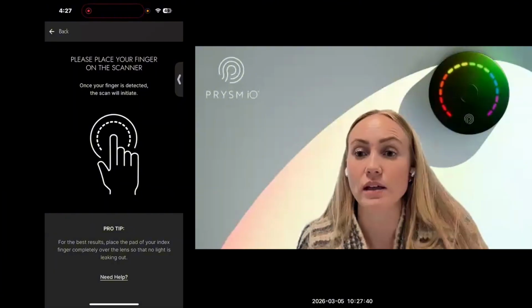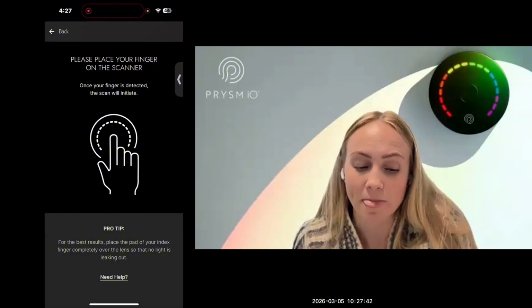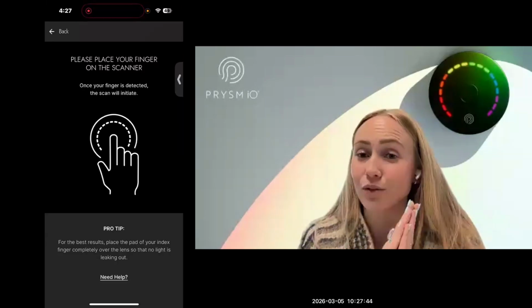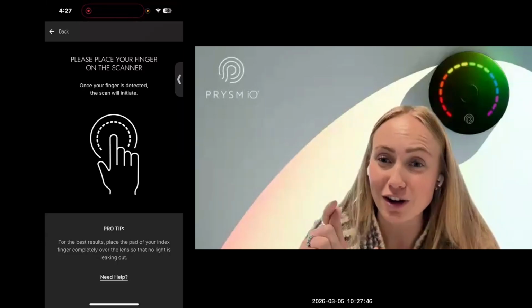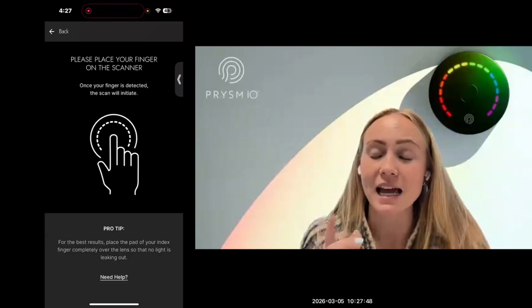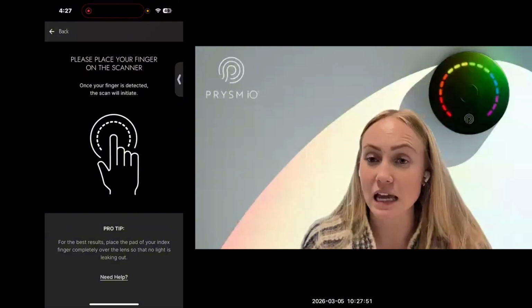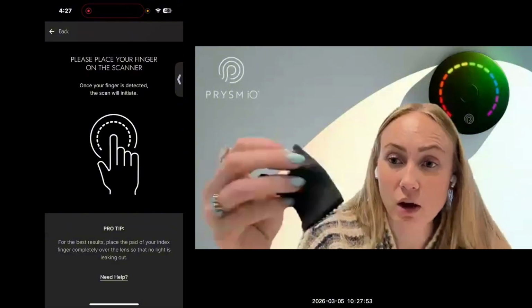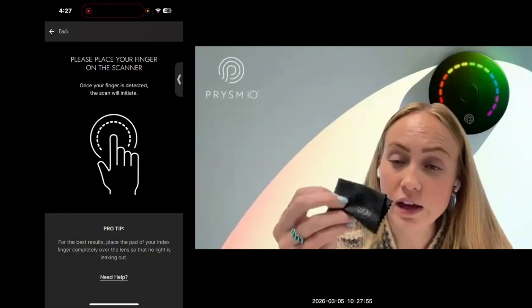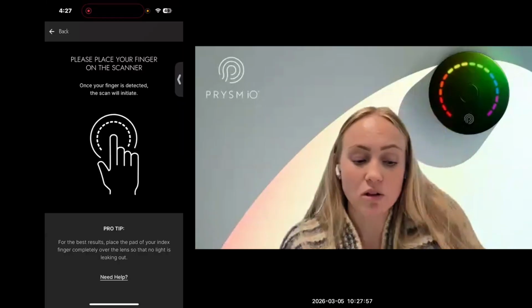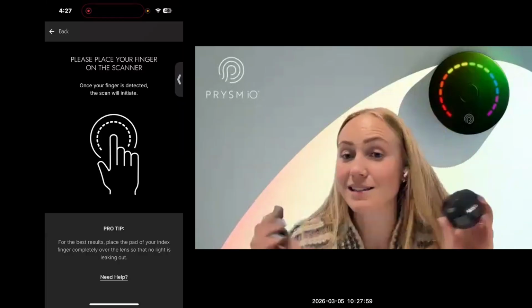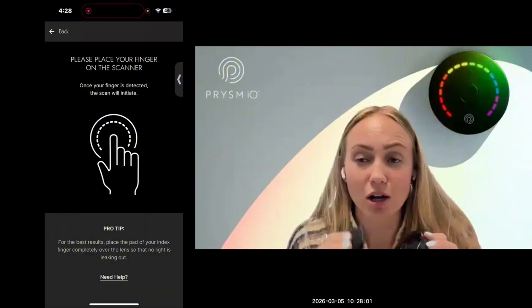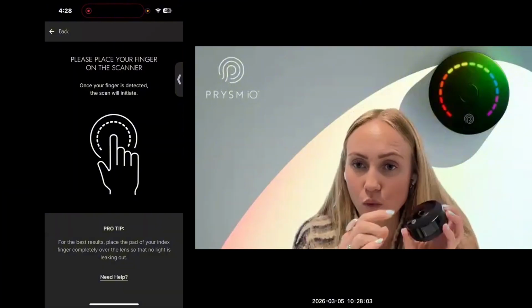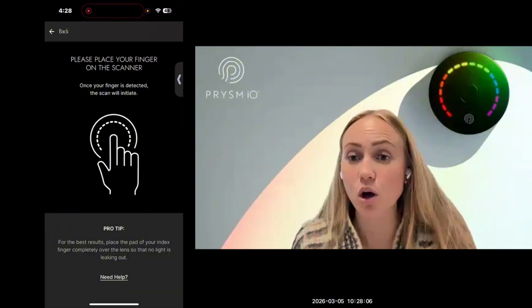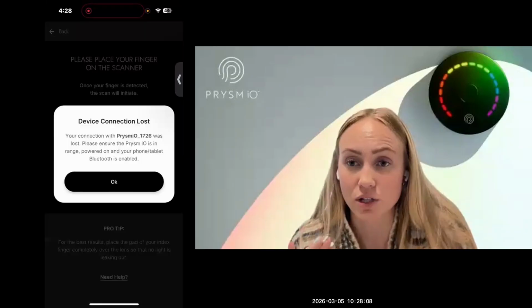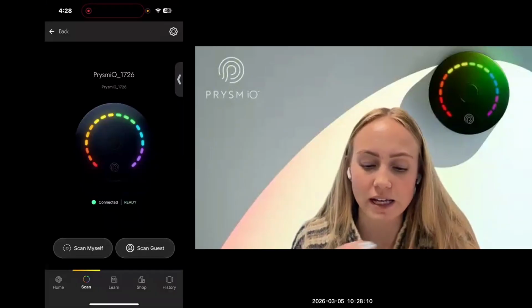The next thing is to make sure the lens on the device is clean as well. You'd be surprised how dirty our fingers are, the fingerprints we leave on that lens. And so that can impact the scan results as well. Every Prysm iO comes with a little microfiber cloth, and you'll want to use that microfiber cloth to wipe the lens. It doesn't take long, just a quick wipe, to make sure there's no residue on there. That will also really help with the scan results. Oh, and I turned off my device.